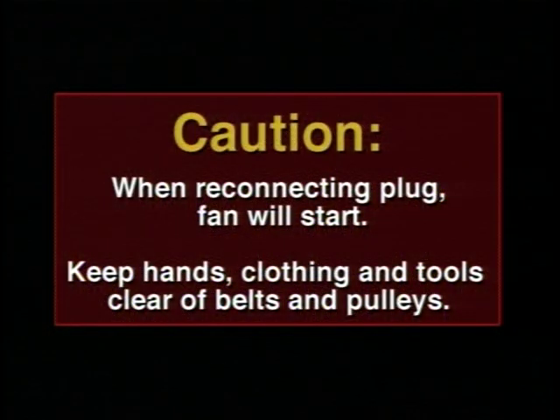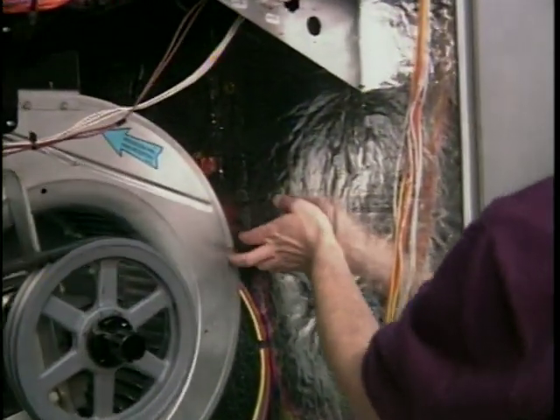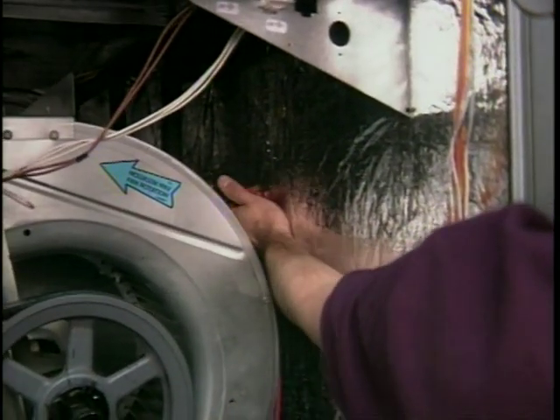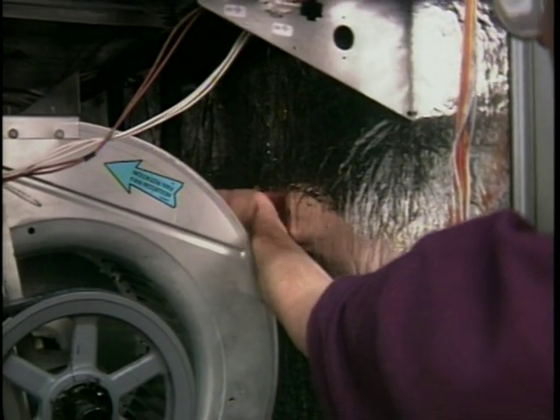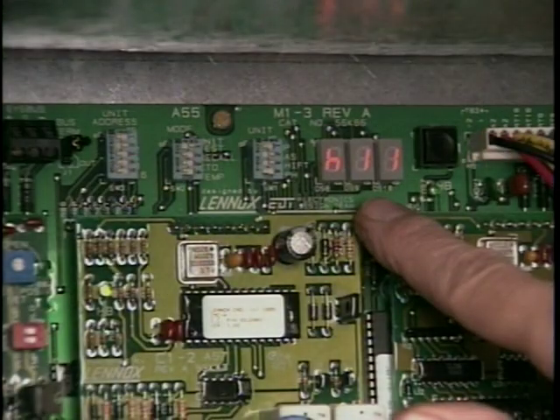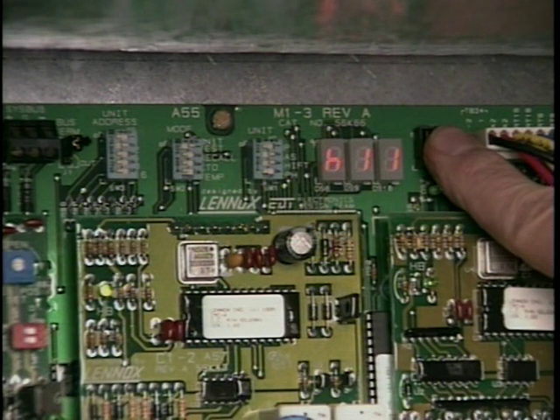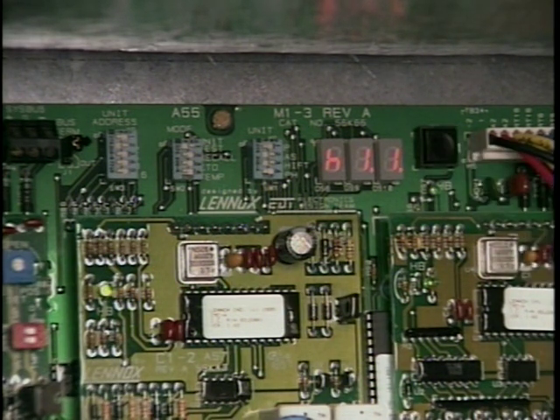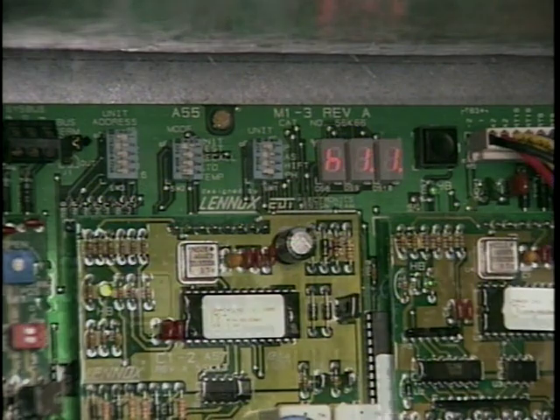Use extreme caution. When the power plug is replaced, the fan will start. Be sure and keep hands, clothing, and tools clear of belts and pulleys. Now open the blower door and reconnect the fan power plug at the bulkhead connector. Close the blower door. Press and hold the display push button until the periods appear in the LED readout. The fan and both stages of heat should come on. Allow the heat to operate for 2 to 3 minutes before taking temperatures.